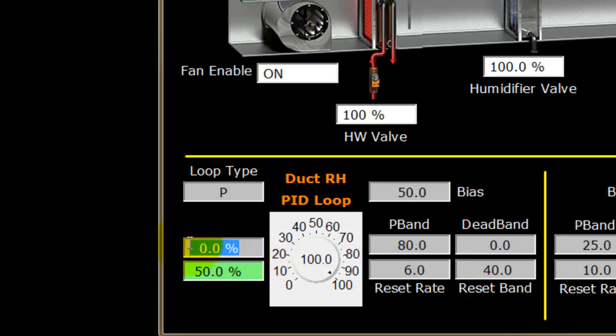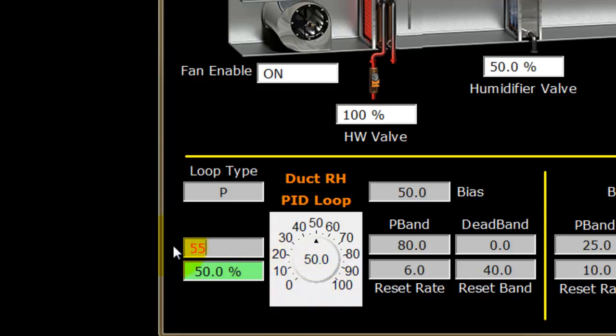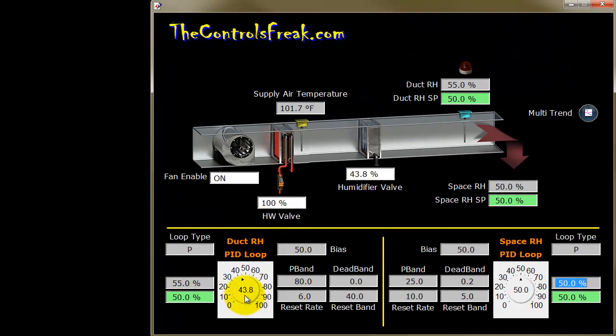If I change the input to 100, it flips around and gives zero percent output. Now, the important thing: let's say humidity begins to rise from 50% to 55%. The loop spits out 43%, which translates to the humidifier valve position. But the proportional-only loop will not continue to adjust. If humidity remains at 55% and never moves, the humidifier valve won't move either — so you'd always be maintaining 55% humidity and never reaching setpoint.